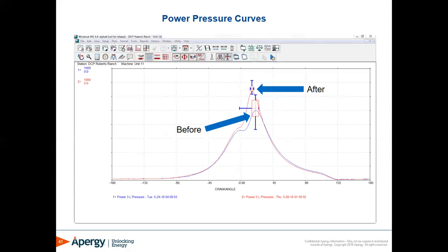Typically, most customers will run conduit above the power cylinders and have a conduit box at each power cylinder. The fuel valve and pressure transducer cables will go into that conduit box, and then inside that conduit will be wiring that goes from our cables back to the cabinet. So on the engine, fuel valve, pressure transducer with the Kiene valve, and then of course the cabinet has to be installed.